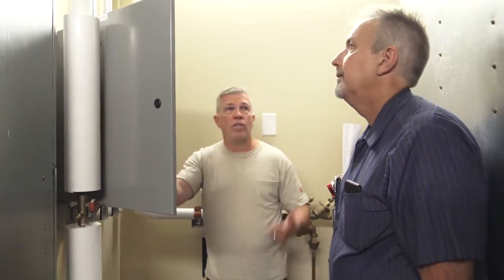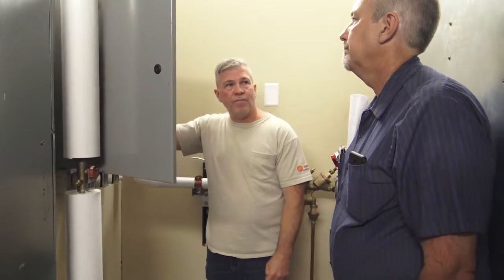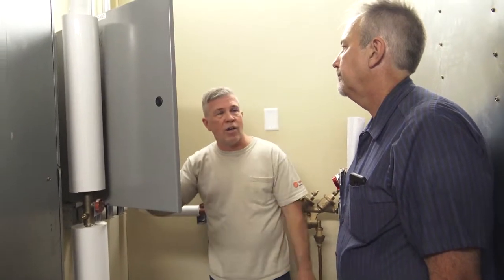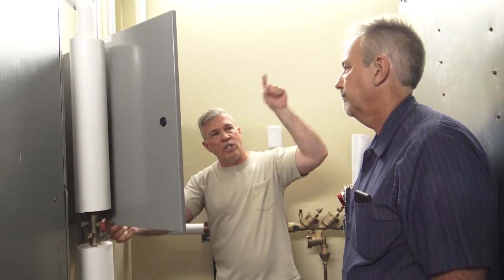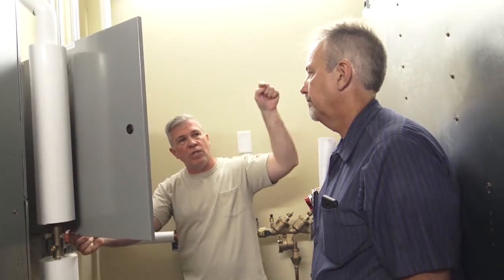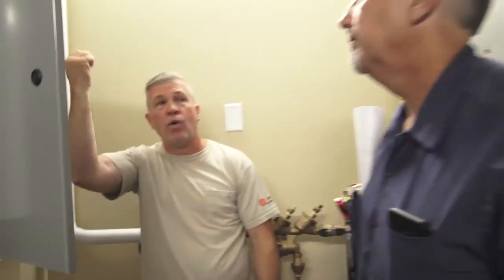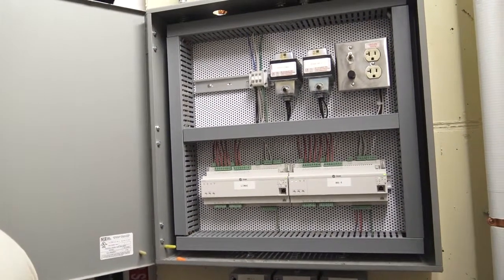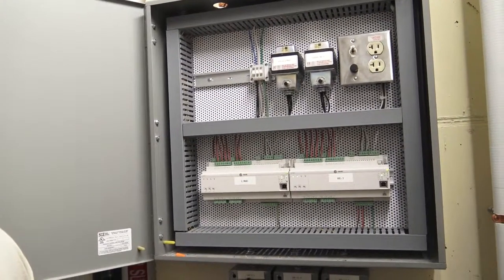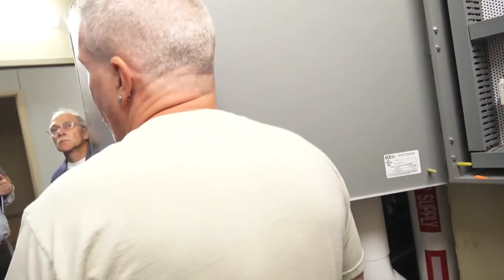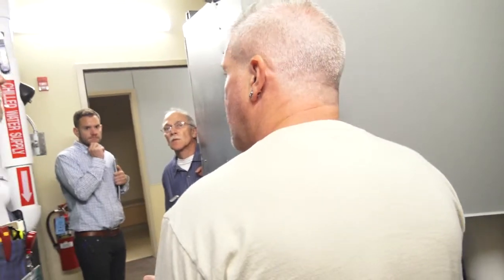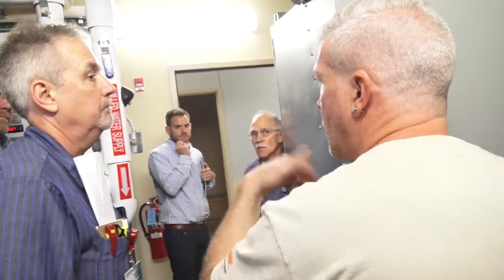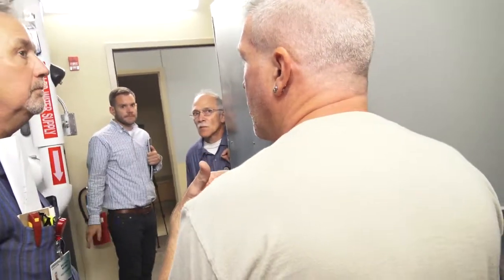And then the two blower coils, one blower coil for each of the vaults, as they call them. There is a VAV that supplies fresh air into the return of the blower coil, and then that gets pulled into the blower coil unit. If you look up, there's a VAV tied into each one of them also. But even if you unoccupy the space, it'll close the VAVs down, but these heat pumps will always stay running all the time for the rooms.